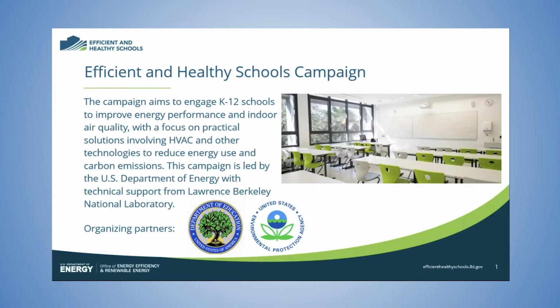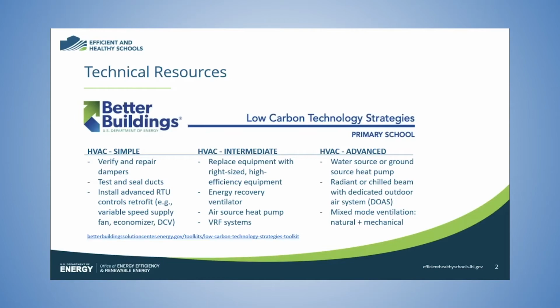So today we've heard many approaches that schools are considering to improve ventilation, filtration, and air cleaning. And we recognize that some of these measures will increase energy use, but note that there are strategies to lower your overall HVAC energy use. There are some relatively simple things you can do, making sure things work, like Sonia was saying: commissioning, making sure your air dampers work, sealing air ducts, and installing advanced controls such as an economizer and making sure that the economizer is working. So all those are relatively simple. And as you think about the greater energy savings that you can achieve from replacing your system, some of the resources that the Department of Energy has, like the Low Carbon Technology Strategy Toolkits, can help give you guidance and good technologies to consider.